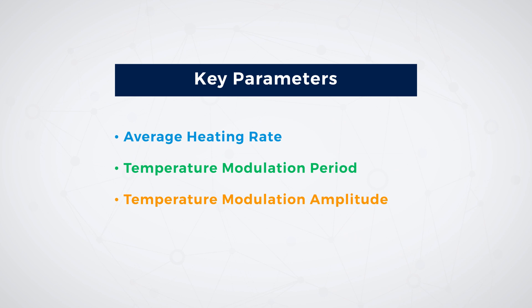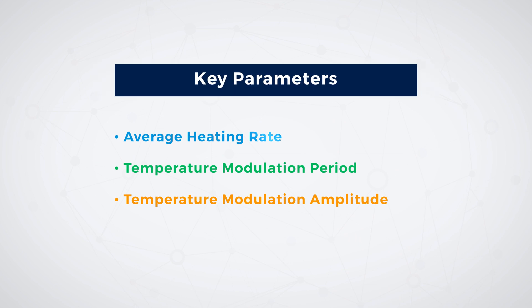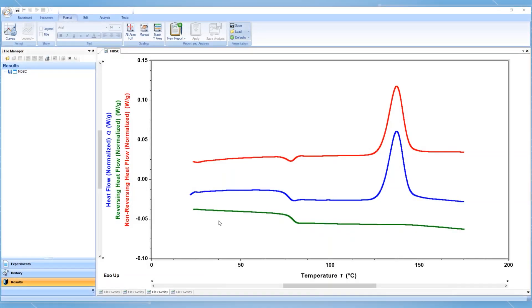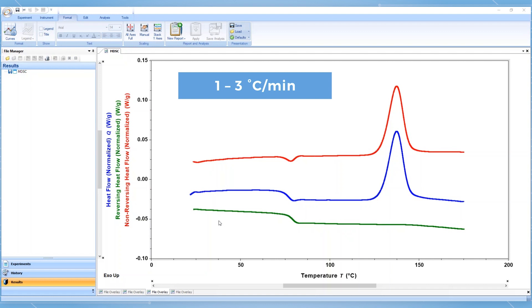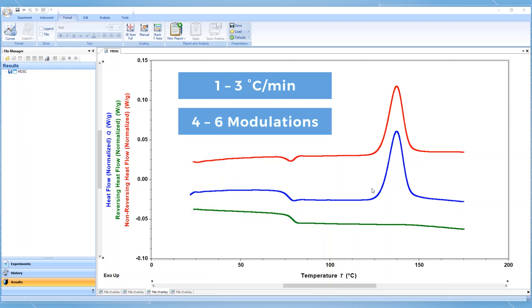To run a modulated DSC experiment, you will need to select three key parameters: the average heating rate, the temperature modulation period, and the temperature modulation amplitude. The average ramp rate of an MDSC experiment is typically between one and three degrees Celsius per minute. To properly separate out reversing and non-reversing heat flow through a thermal transition, a minimum of four to six full modulations should be achieved through the transition of interest.